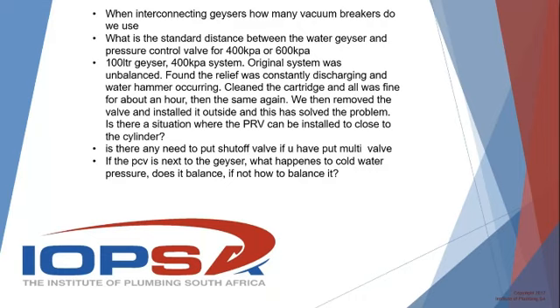Yeah, okay, quite right. If the PCV is next to the geyser, what happens to the cold water pressure? Does it balance, or if not, how to balance it? Guys, I think that's a basic plumbing 101 configuration situation. The basic premise of balanced water, and we know that balanced water pressure isn't as simple as just saying, well, I've taken it off after the PRV, but the basic premise is that the hot and cold water are at the same pressures, in other words, the pressures are regulated by, in most cases, a common PCV. In other words, you simply T and take the cold water supply to the points off after the PCV. That doesn't constitute 100% balanced pressure, but anyway, that's the situation.